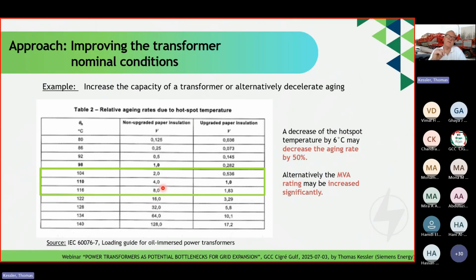Or alternatively, you can increase the power, the MVA rating of the transformer accordingly. So this is about decreasing the aging rate - that is the physical background behind the lifetime extension and rejuvenation of installed base transformers.